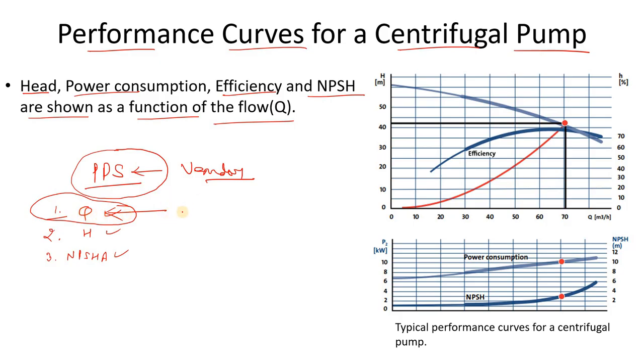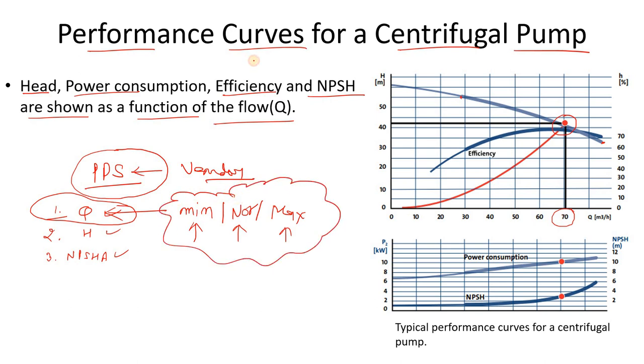Whenever we specify the flow rate, we provide it in three ranges: minimum, normal, and maximum. For example, your normal flow rate could be 70, your maximum flow rate could be around 84, and your minimum could be around 30. These ranges appear directly on the performance curve. Flow rate is the key function for each type of pump curve, and selecting the right capacity is very important when selecting a pump.